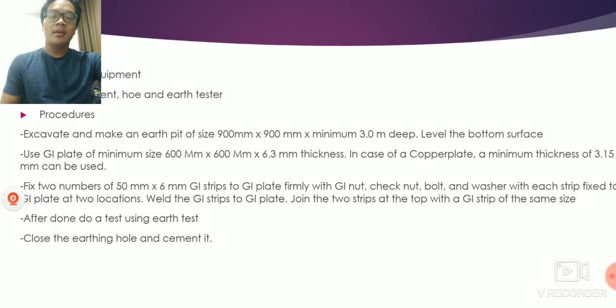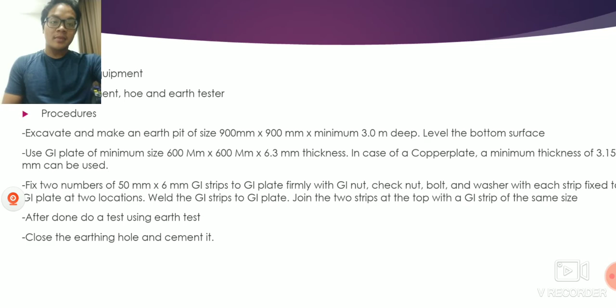Procedure: excavate and make an earth pit of size 900mm by 900mm by a minimum of 3.0 meters deep. Level the bottom surface. Use a GI plate of minimum size 600mm by 600mm by 6.3mm thickness, in case of a copper plate.